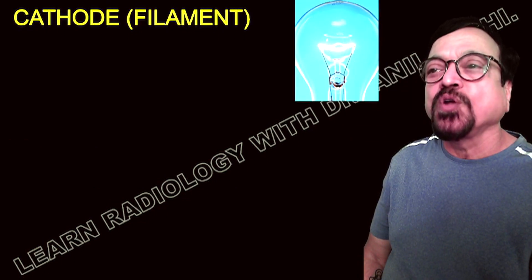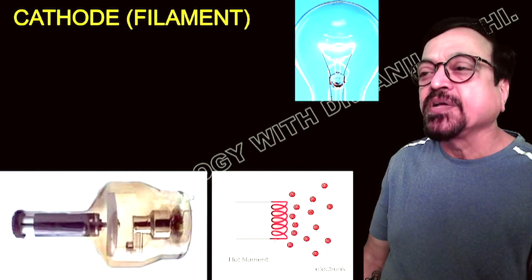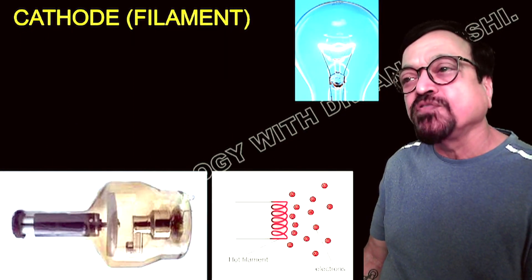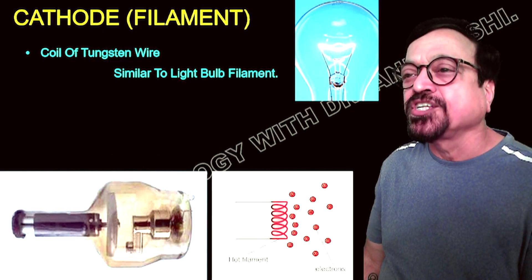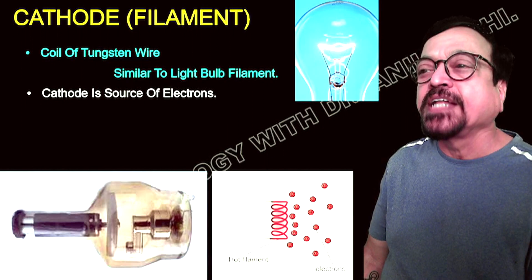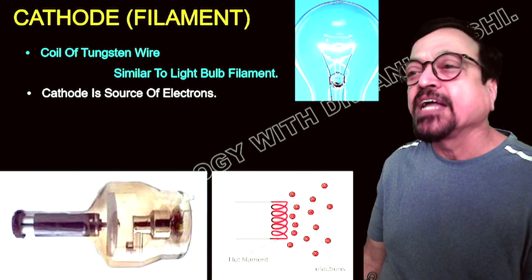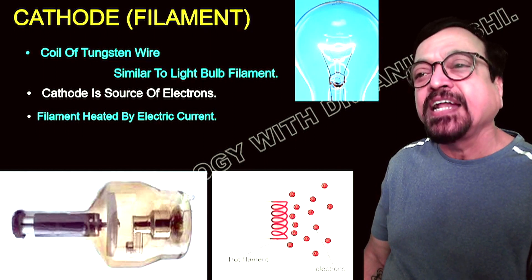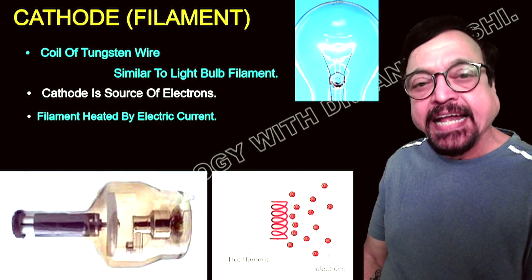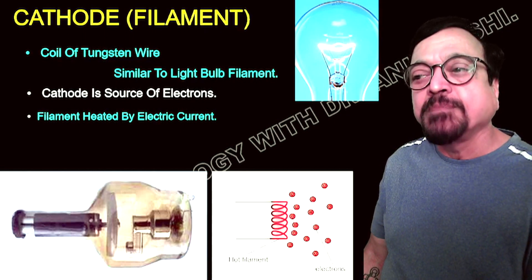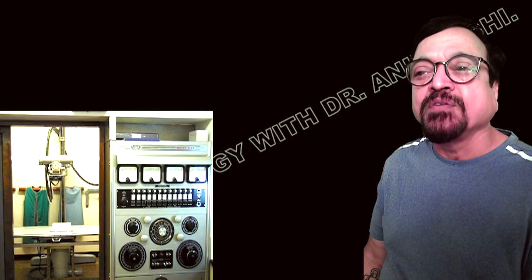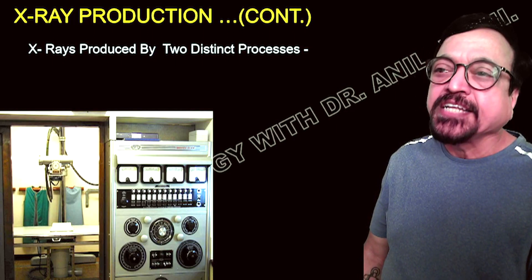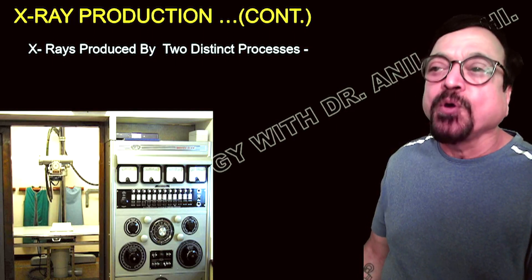The material usually used for the filament is tungsten, because of its high melting point — since a large amount of heat is involved, it should not melt. The cathode filament's main role is to supply electrons. When it is heated, it boils off electrons which are available for x-ray production. The cathode is a coil of tungsten wire, similar to an electrical bulb, and is the source of electrons by means of thermionic emission. The filament is heated by electric current; when it boils off, it releases electrons which are then converted into x-ray photons.